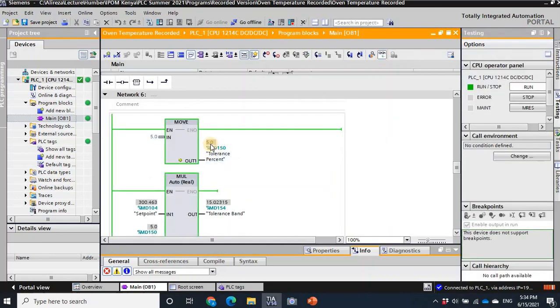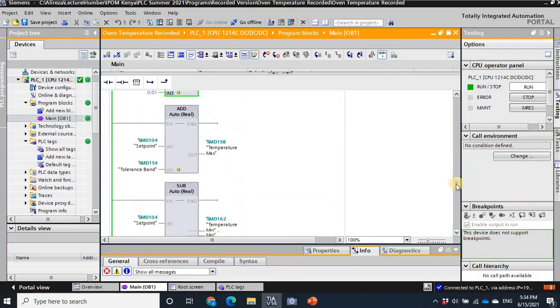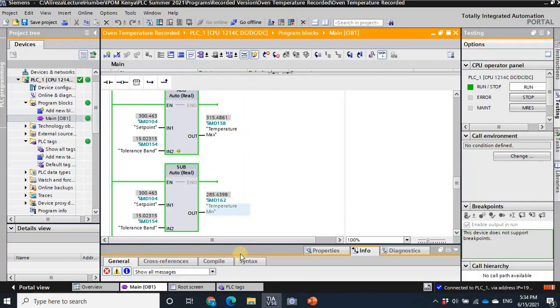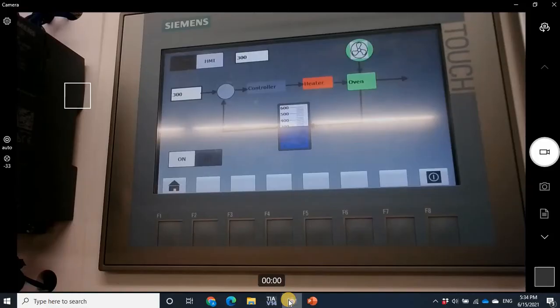Now the tolerance percent is five and the tolerance band is correctly 15 degrees — 15 degrees more or less than the set point. Checking the camera, the oven is now green. That's working correctly.